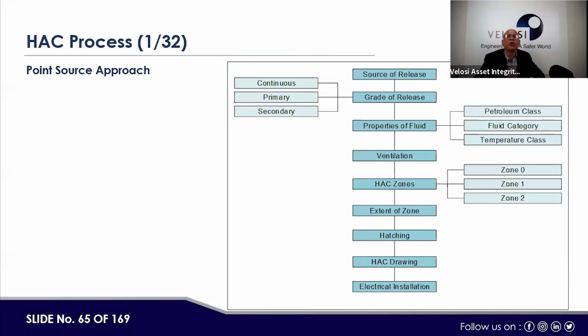So now we are giving an example for the point source approach. In that, first of all, fluid-wise: continuous, primary, secondary. Continuous means inside the equipment. Primary means around up to 2 meters, 3 meters. Secondary means where fluid can reach sometimes. Other details will also come. So source of release, grade of release, which is here.